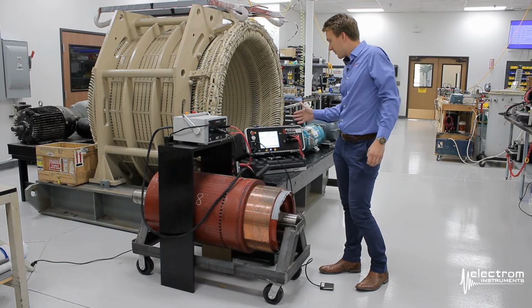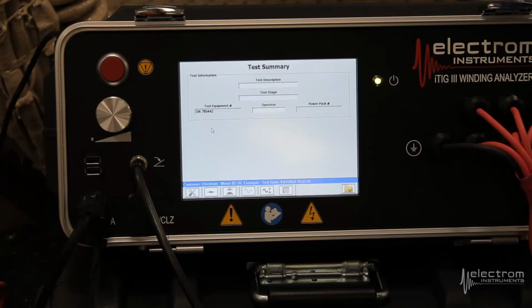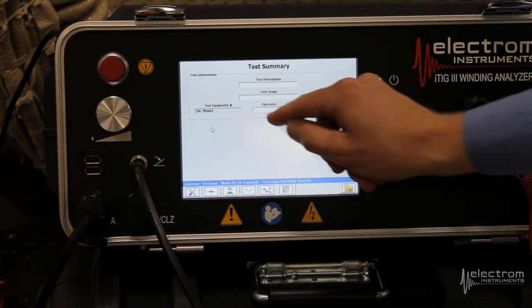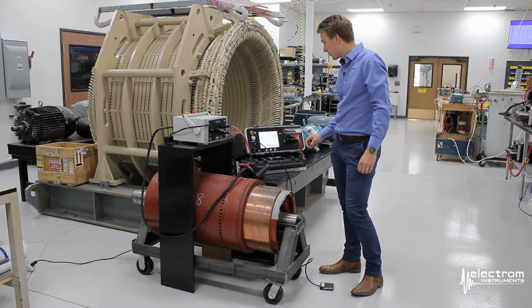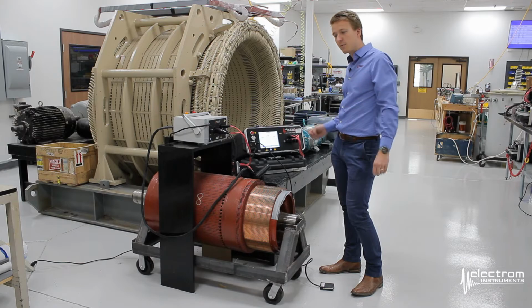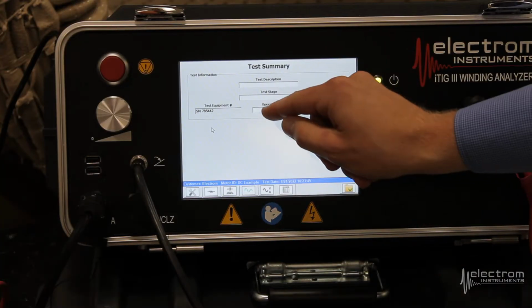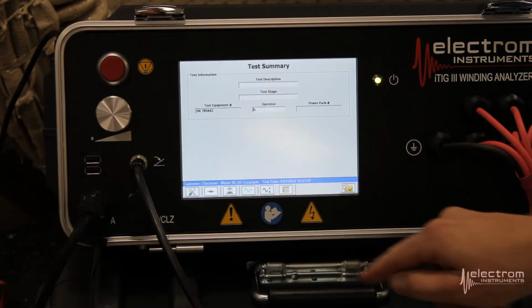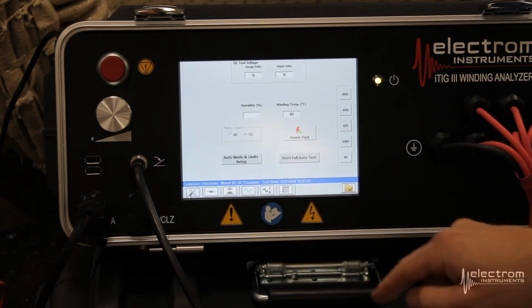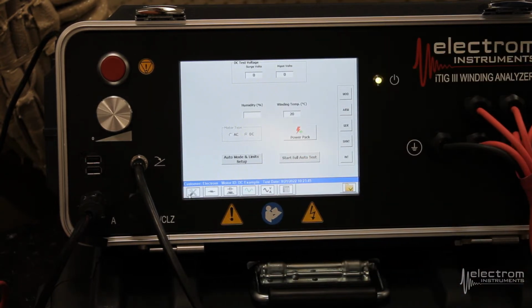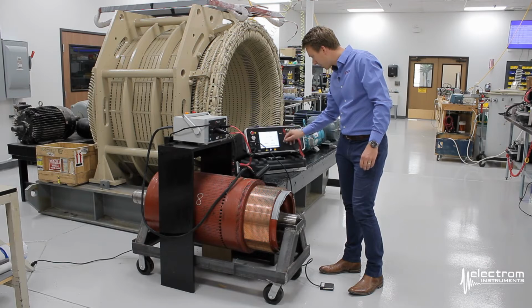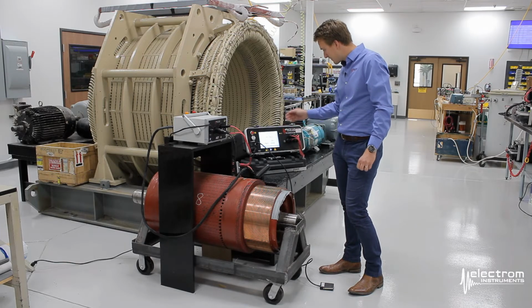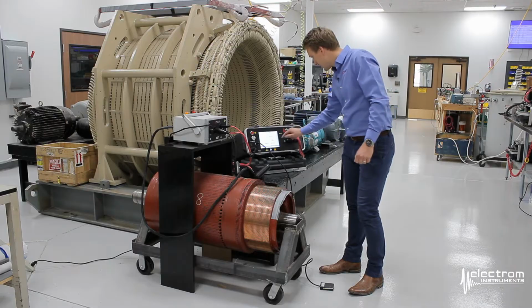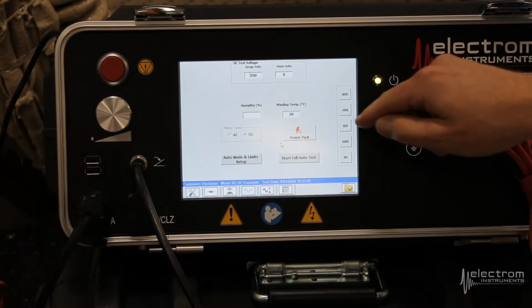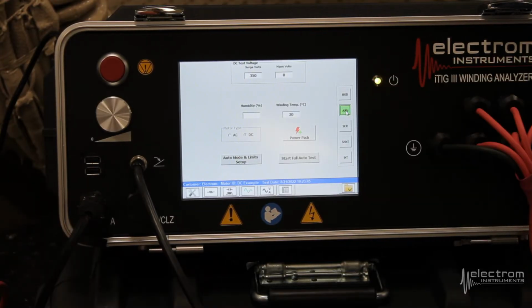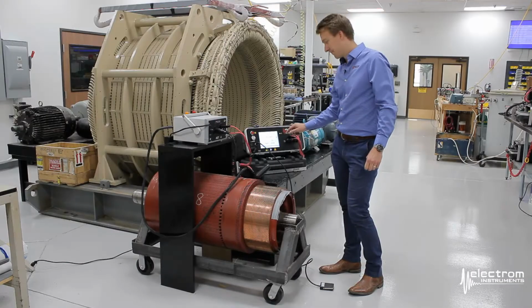As with the other videos, we end up in the test summary tab. We can add some information here about what we're testing, what description, what stage we're at. I'm going to add the operator information here, for example. And then you'll see on the next screen, the setup screen, that we can select from a list of predefined components of the DC motor. So in this case, we're going to test the armature. This will actually now be populated in the test description field automatically.